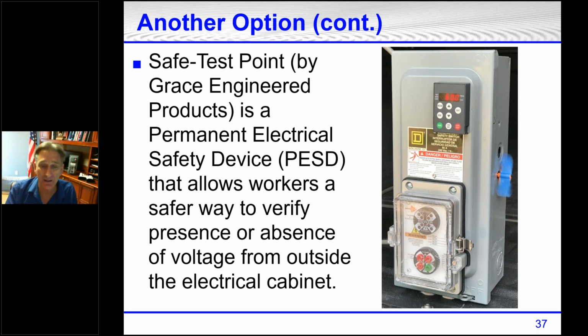It's got the lights on it. It has a safe voltage indicator, lights, and the safe test point on it, where when I de-energize this box, standing on the outside of this box, I can test for the absence of voltage, phase to phase and phase to ground.